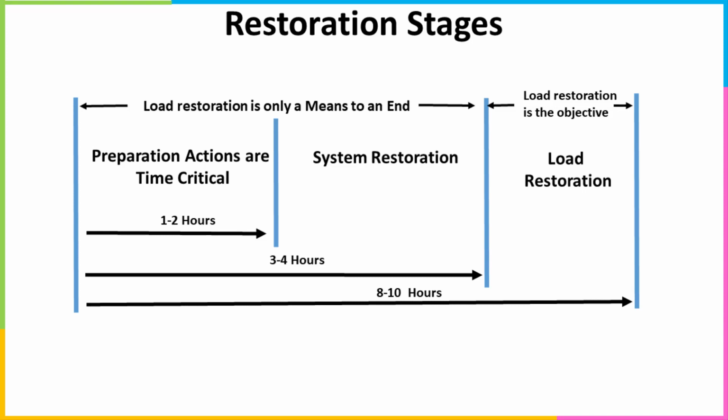So this is just a schematic. It depends upon the system. Some systems which are completely hydro-based can be brought back in service within 30 minutes. Some which are completely dependent on thermal may take further time. Systems which are completely dependent on renewables may also take a lot of time to bring back. So this depends upon the type of system, the type of generation available, and the type of connectivity available to restore the system.